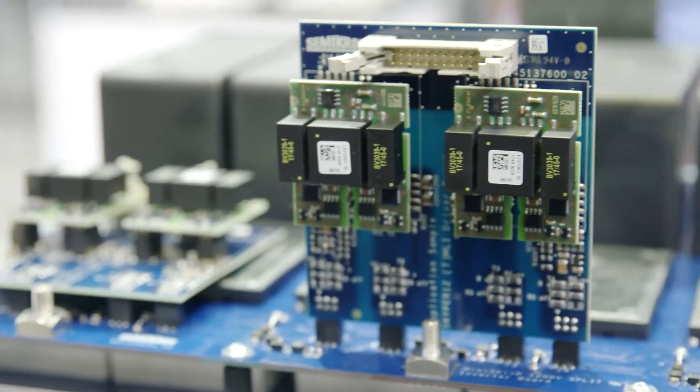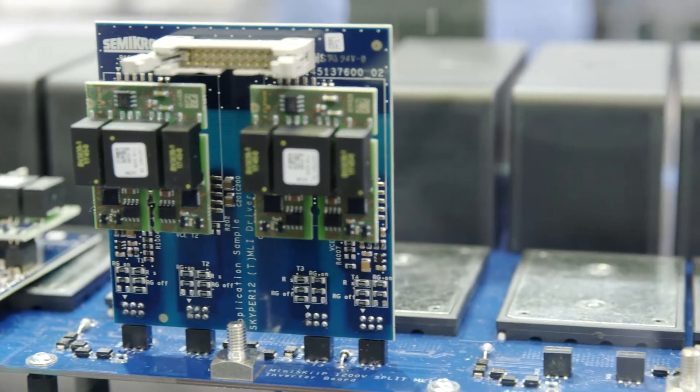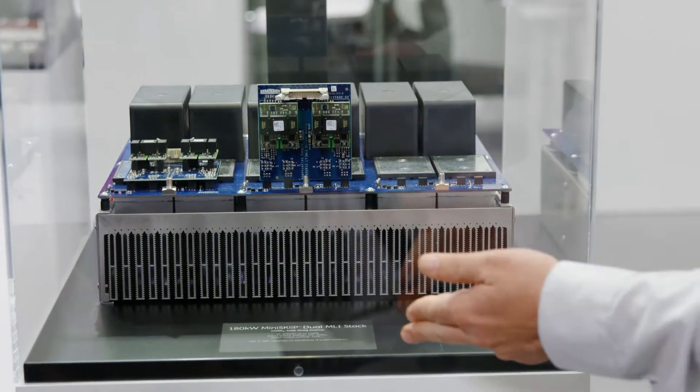Here we take the MiniSKiiP dual split MLI module — that means we have a MiniSKiiP module in NPC topology, in a split NPC topology for direct PCB mounting and a base plate-less module. And this enables a 1500 volt PV stack up to 180 kilowatts.